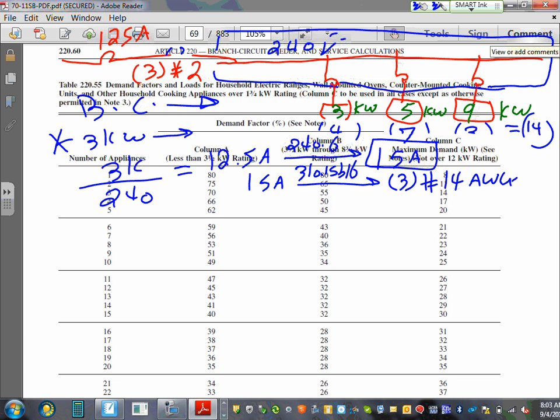All these will be the same branch circuits, right? I mean the same type of branch circuits. So I have a 3 kW branch circuit. You take it divided by 240. Why 240? We're burning them at 240. I know that. I'm telling you. 12.5. The next standard overcurrent protection device is 15 amp, 310.15(B)(16), under the 60-degree column. What do you get? 60-degree column. You get 3 conductors, number 14.